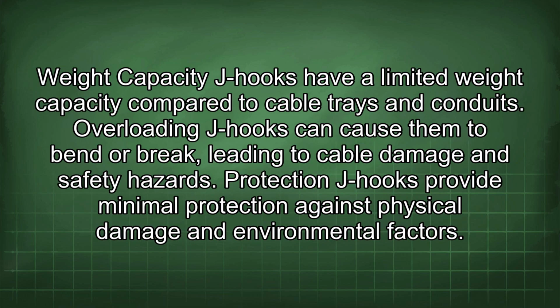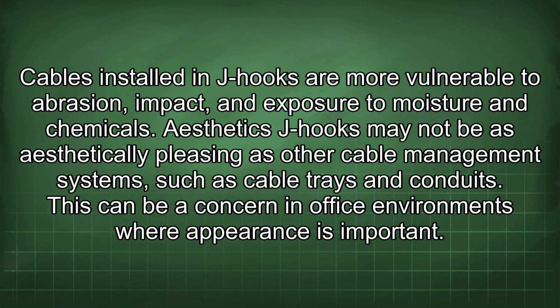Weight capacity: J-hooks have a limited weight capacity compared to cable trays and conduits. Overloading J-hooks can cause them to bend or break, leading to cable damage and safety hazards. Protection: J-hooks provide minimal protection against physical damage and environmental factors. Cables installed in J-hooks are more vulnerable to abrasion, impact, and exposure to moisture and chemicals.